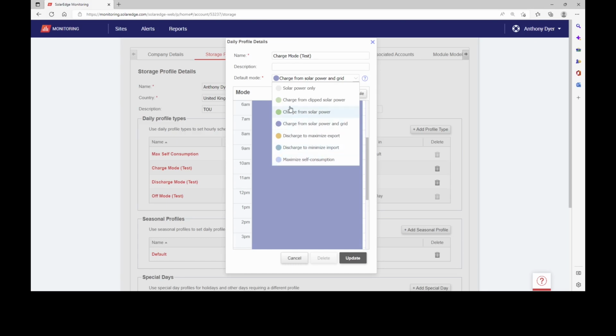Now there are other modes which are very interesting here. We've got charge from clipped solar power. This will maximize production if your inverter is export limited. For example, with this site, we're limited to 5 kilowatts of export, so if there's available production above that, say 6 kilowatts, then 1 kilowatt of that will go into the battery. This is a very useful mode to have anytime from mid-spring to early autumn.